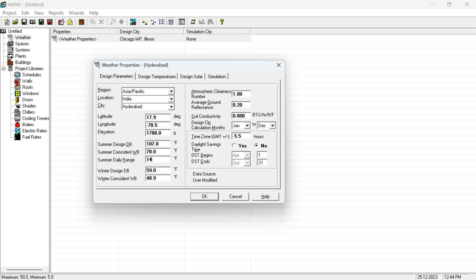From the ASHRAE Handbook, the latitude of Hyderabad is approximately 17.86 and the longitude is approximately 78.47. The elevation of Hyderabad — altitude from sea level — is 1788 feet. The summer dry-bulb temperature is 107°F, wet-bulb temperature is around 78°F, and the daily range is 14°F.